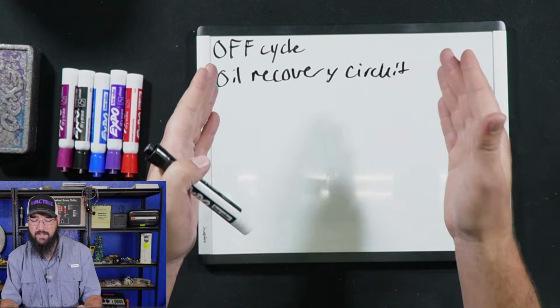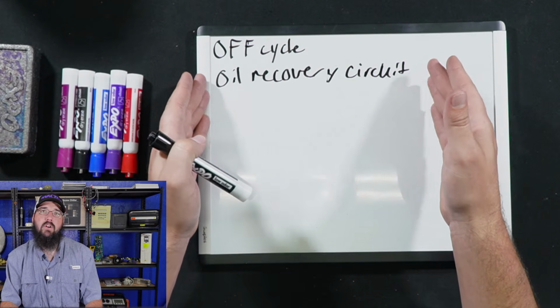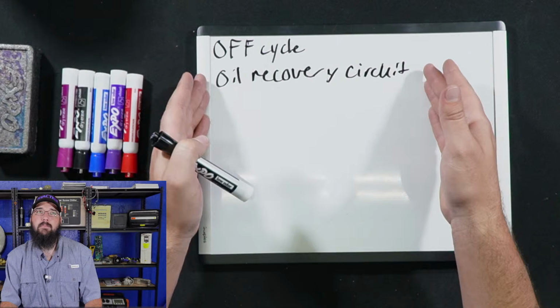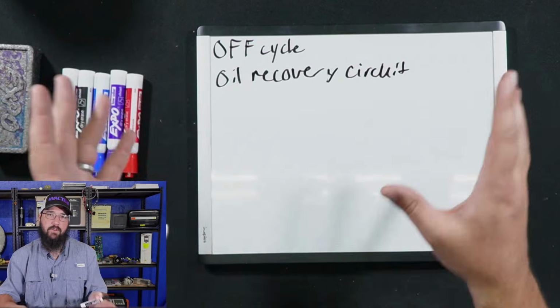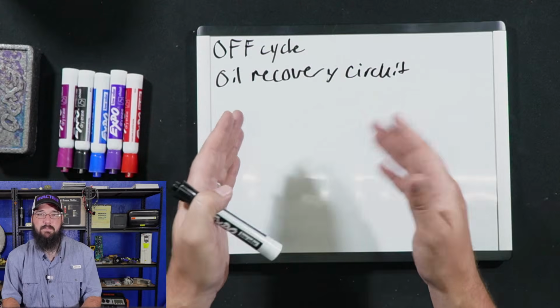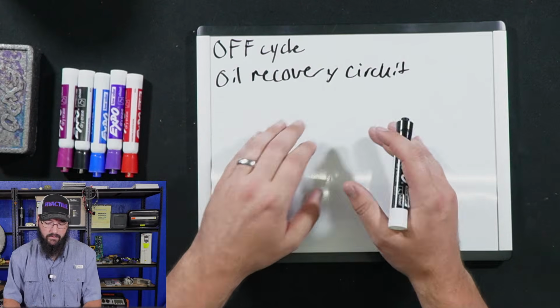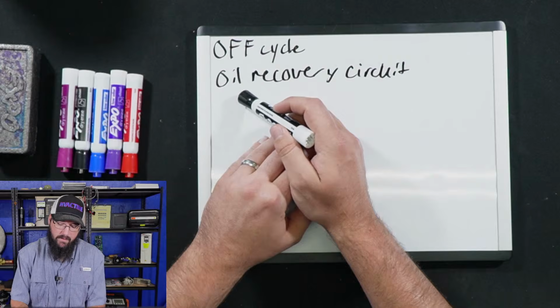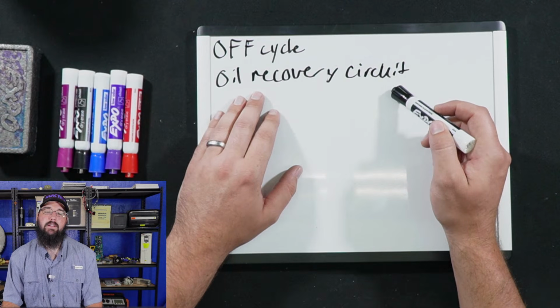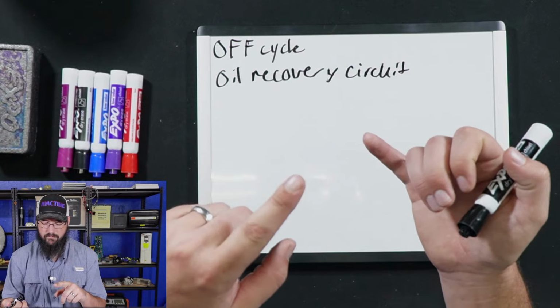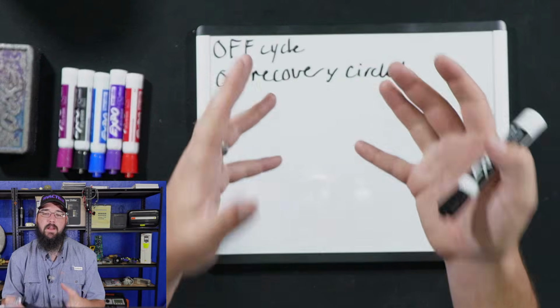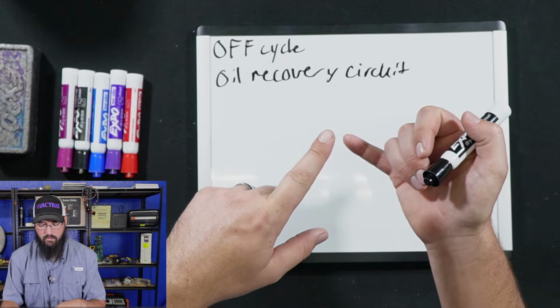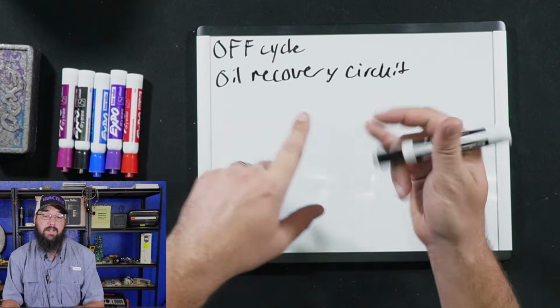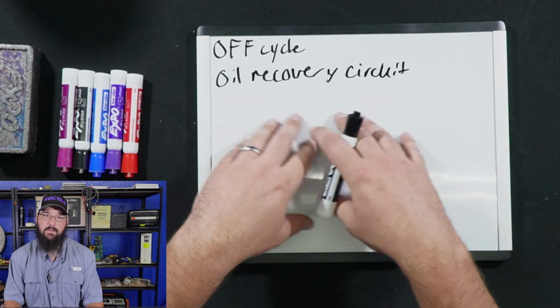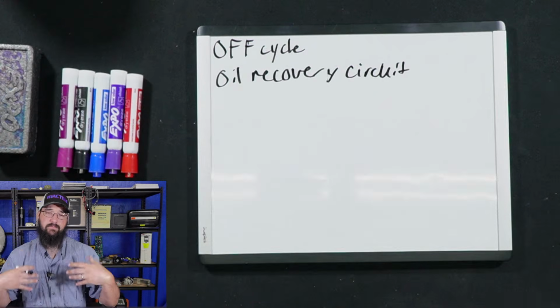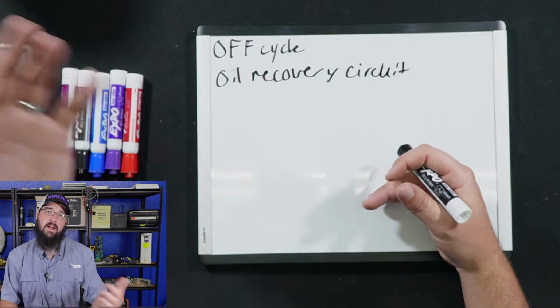Anyway, so an RTHD, a RTAC, RTAF, I think even the RTAEs, all of those are using a type of gas pump style oil recovery system. Anyway, if this isn't functioning correctly, then that can cause the migration problem. So ways it could malfunction. One, the eductor filter. So these will have some kind of filter dryer involved. That could be plugging up, not allowing enough flow through.